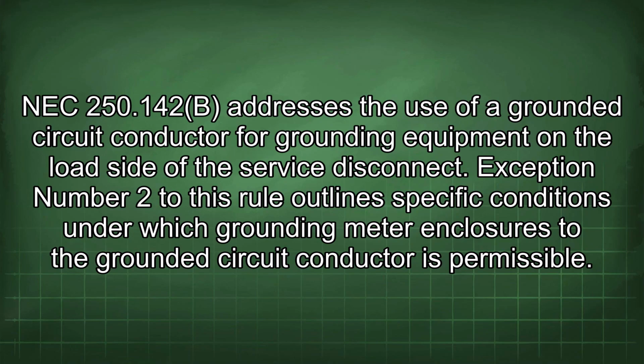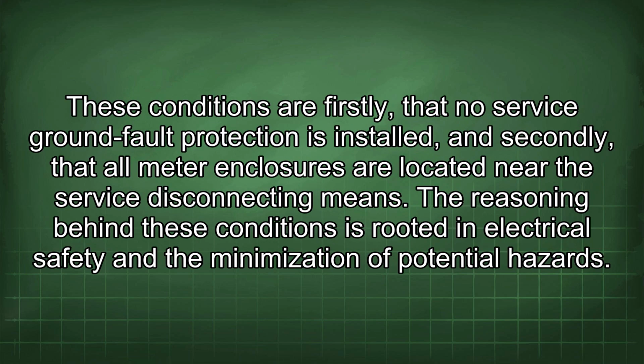250.142(B) addresses the use of a grounded circuit conductor for grounding equipment on the load side of the service disconnect. Exception number 2 to this rule outlines specific conditions under which grounding meter enclosures to the grounded circuit conductor is permissible. These conditions are, firstly, that no service ground fault protection is installed, and secondly, that all meter enclosures are located near the service disconnecting means.